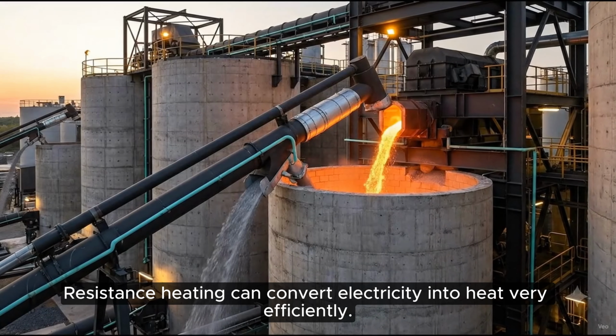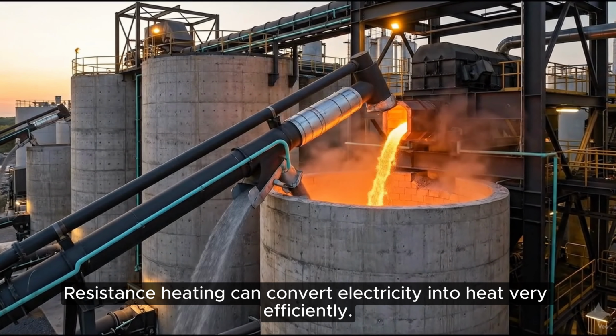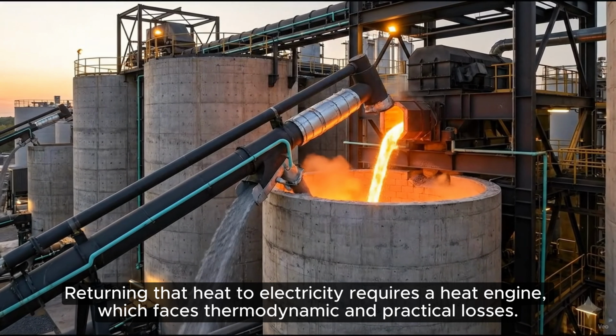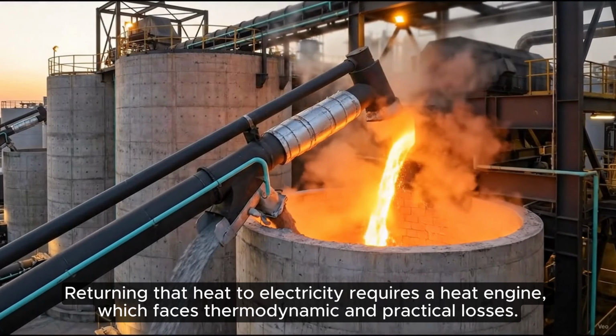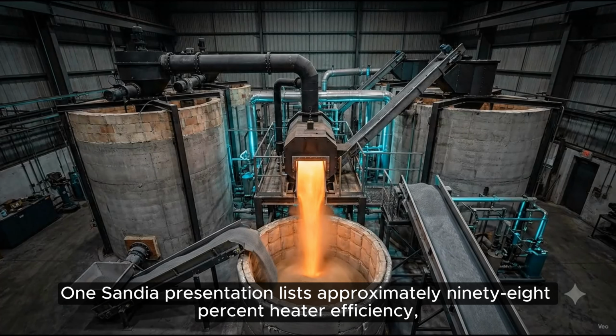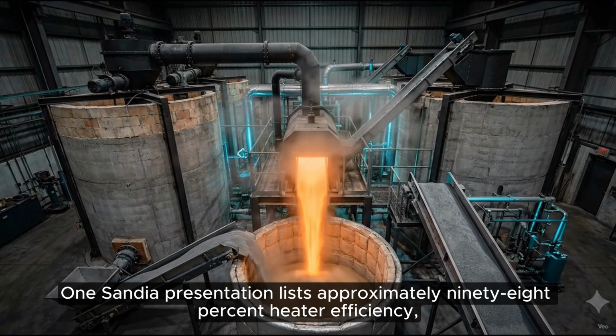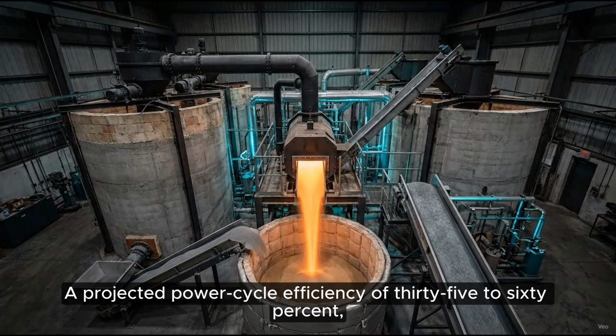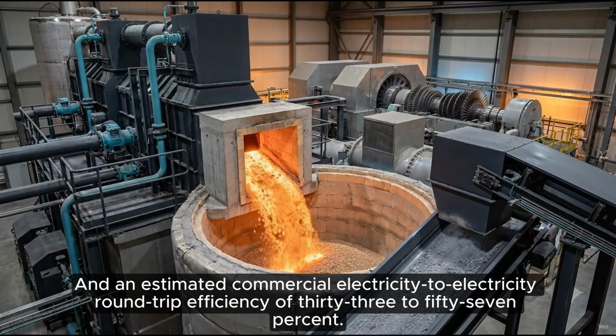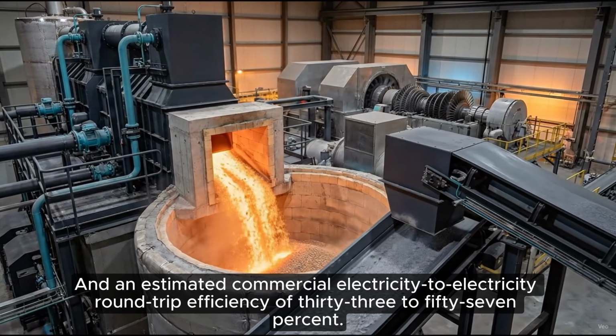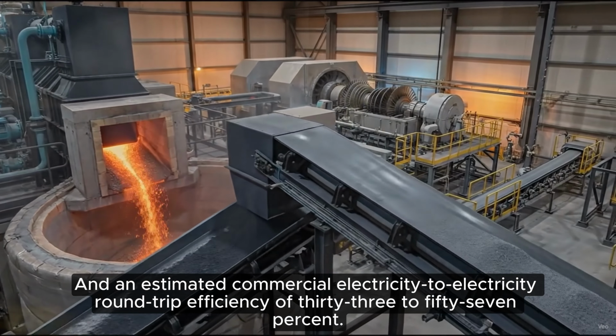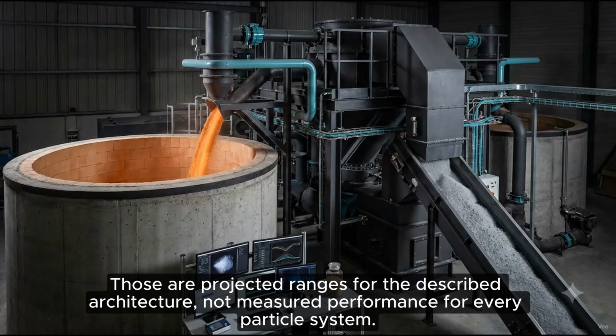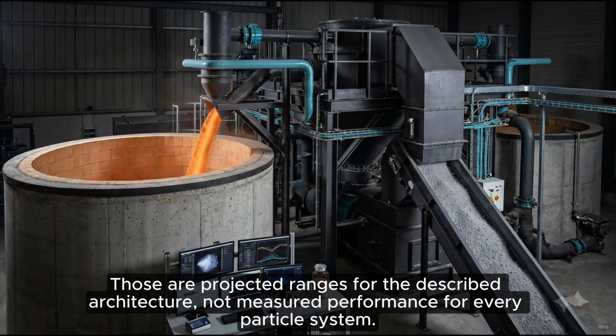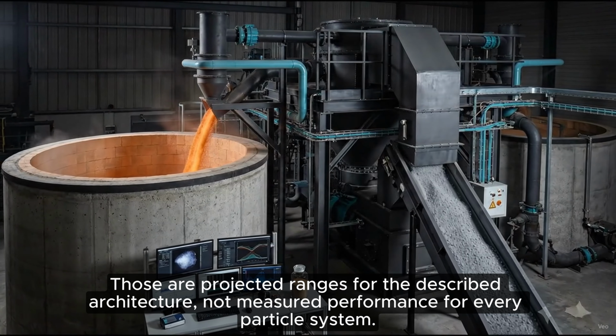Two efficiencies must remain separate. Resistance heating can convert electricity into heat very efficiently. Returning that heat to electricity requires a heat engine, which faces thermodynamic and practical losses. One Sandia presentation lists approximately 98% heater efficiency, a projected power cycle efficiency of 35 to 60%, and an estimated commercial electricity to electricity round-trip efficiency of 33 to 57%. Those are projected ranges for the described architecture, not measured performance for every particle system.